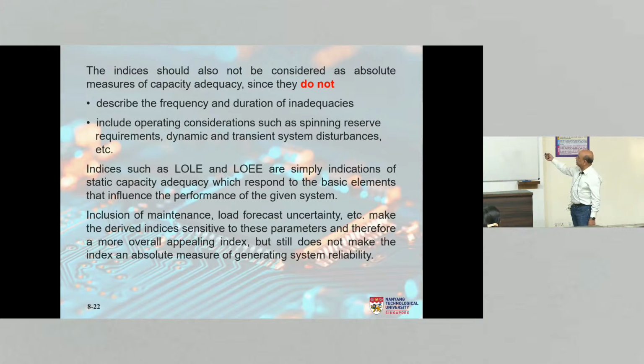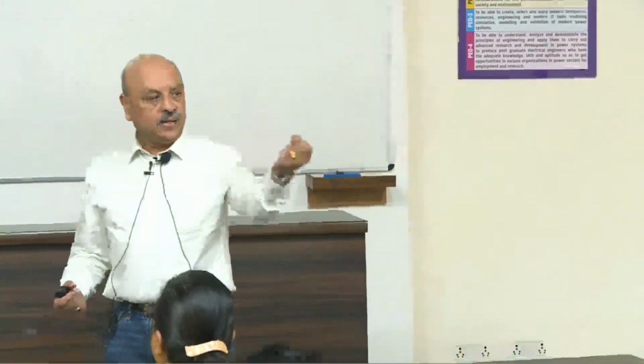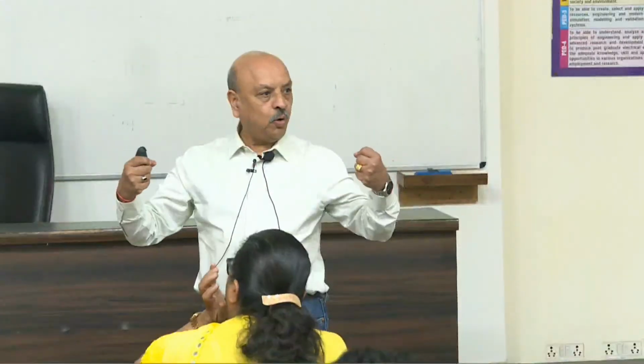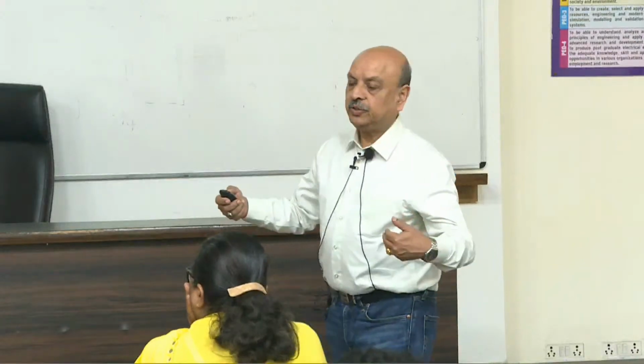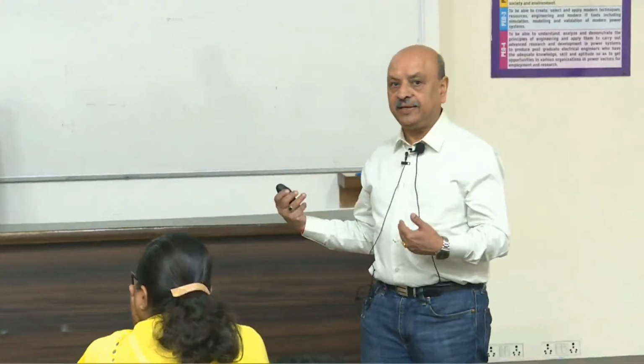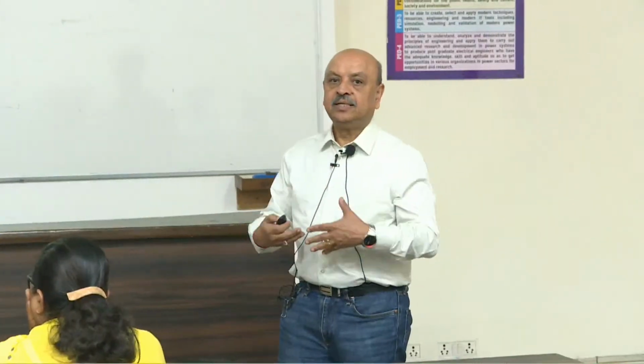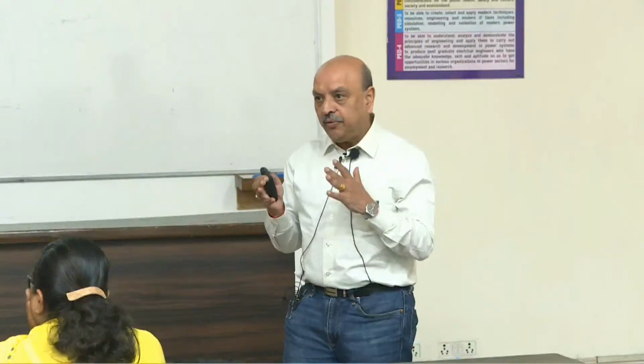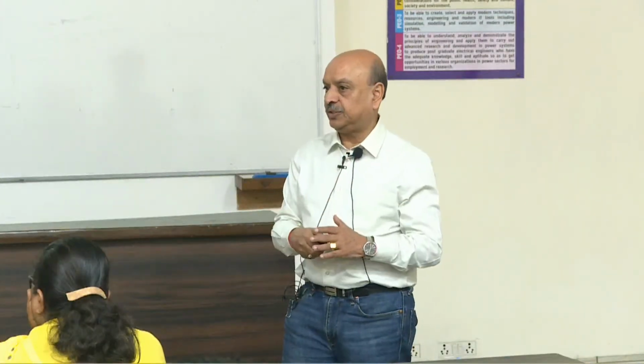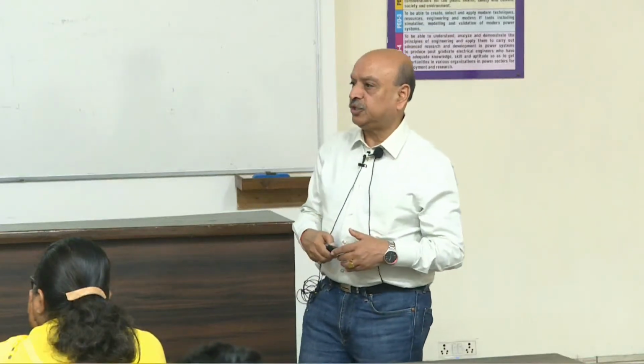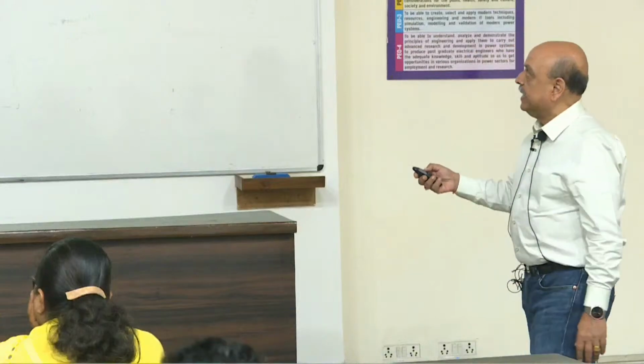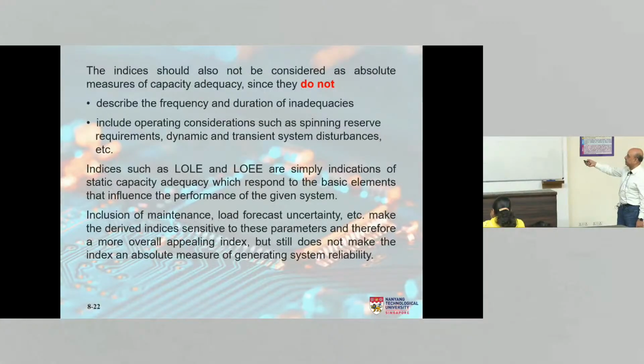We are not including operating considerations such as spinning reserve, dynamic and transient disturbances. I again refer you to the definition of reliability. It has two components, adequacy and security. We are dealing with only adequacy here, right? Not security. So therefore, the reliability indices that we are calculating here are not 100% representative of the entire system. They are only representing the static capacity evaluation, not the spinning reserve, not the dynamic nature of the system, not the security aspect. Indices such as LOLE and LOEE are simply indications of static capacity adequacy, which is what I just said, which respond to the basic elements affecting the performance of the system.